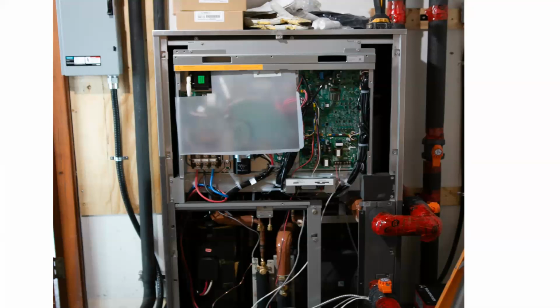That's a hard one to call because we've been going through seasonal changes, as we speak. But from the time we started the system, we've seen a constant decrease in the amount of power required. We're trying to get to a baseline, and we're not quite there yet. We're almost at the neutral season where we're not heating or cooling. We don't expect the cooling costs, which used to be very high, because going into summer you use a lot more electricity with just air conditioning systems.